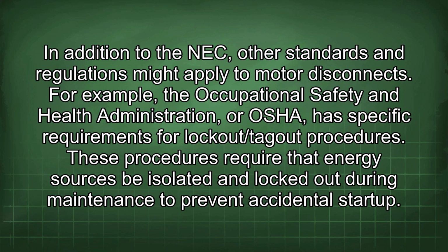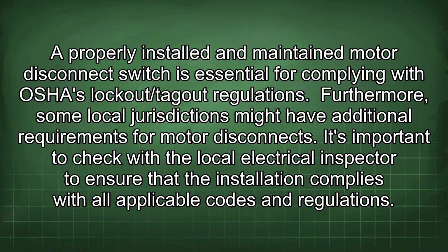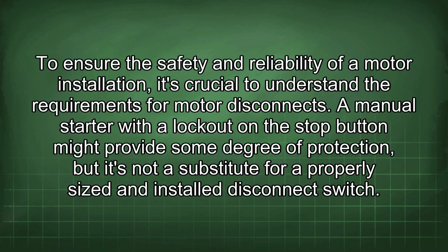For example, the Occupational Safety and Health Administration, or OSHA, has specific requirements for lockout/tagout procedures. These procedures require that energy sources be isolated and locked out during maintenance to prevent accidental startup. A properly installed and maintained motor disconnect switch is essential for complying with OSHA's lockout/tagout regulations. Furthermore, some local jurisdictions might have additional requirements for motor disconnects. It's important to check with the local electrical inspector to ensure that the installation complies with all applicable codes and regulations. To ensure the safety and reliability of a motor installation, it's crucial to understand the requirements for motor disconnects.